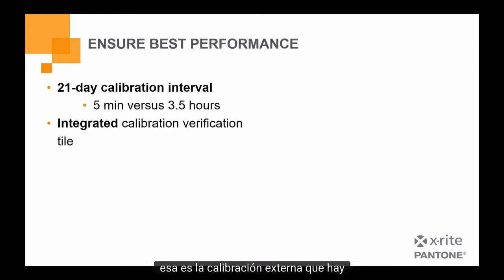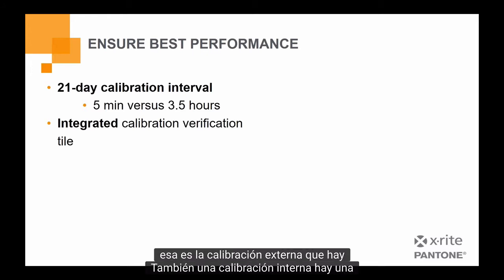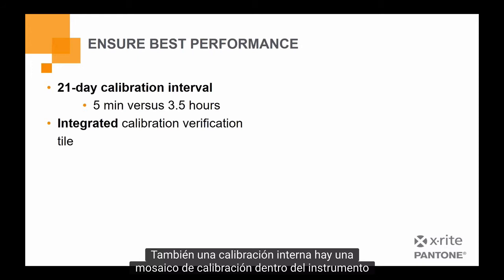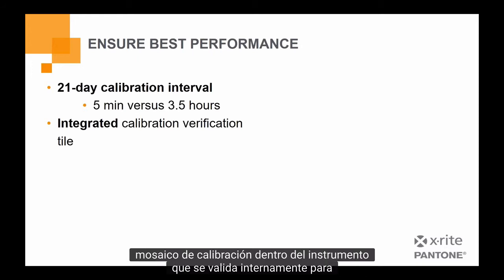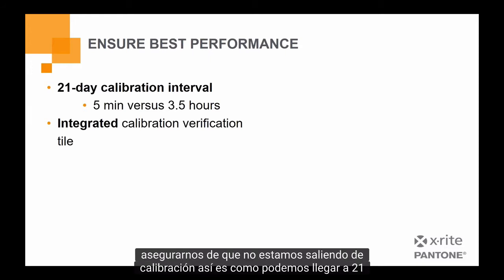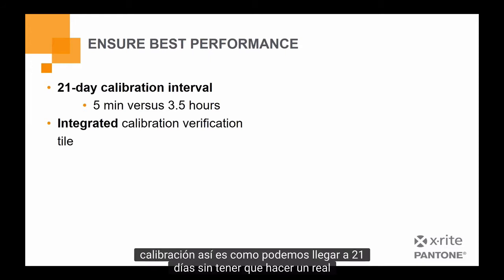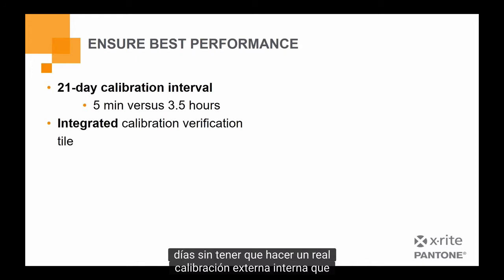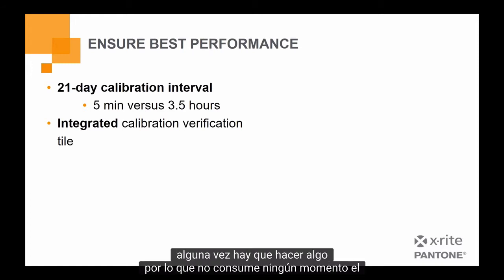Now, that's the external calibration. There's also an internal calibration. There's a calibration tile inside the instrument that is being validated internally to ensure we aren't drifting out of calibration. That's how we can go to 21 days without having to do an actual internal or external calibration. That internal calibration happens without you ever having to do anything, so it doesn't consume any time.